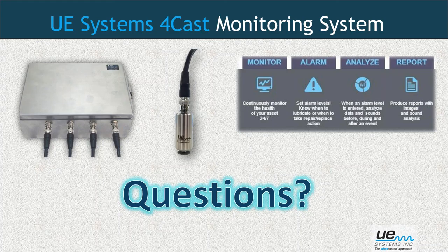Sure, the temperature one's easy, I'll address that first. We've got what we call a thermal isolation yoke - essentially a little air radiator that you mount on the motor or gearbox, wherever it's too hot for the sensor to be. Then you mount the sensor on it. That lets you get up to 600 degrees F surface temperature with no danger of damaging the sensor. So that's an easy fix - we've got a lot of those in place currently and they work extremely well. It's easy to mount and use, it has some fins on it and reduces the temperature down.